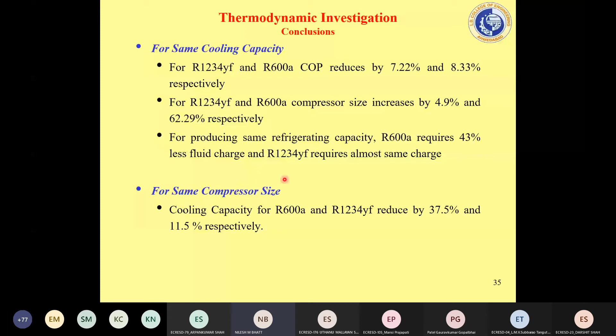And for the same compressor size, the cooling capacity for R600A is almost 40% lower, while the reduction in capacity is just about 12% for YF. From this conclusion, many argue why to have a loss of 11%, why to have a loss of 12%. But as I mentioned earlier, ISHRAE and ASHRAE say that your environmental factor is dominant rather than thermophysical property and only the performance. So now, through the concept of total equivalent warming impact, we will try to understand that though the performance of the refrigerator with YF deteriorates by 12%, overall its performance is comparable, or rather slightly better than R134A.